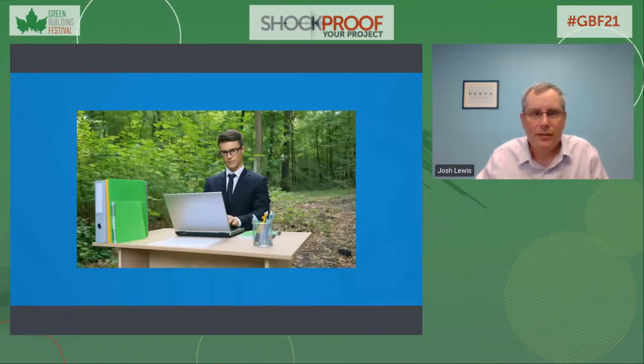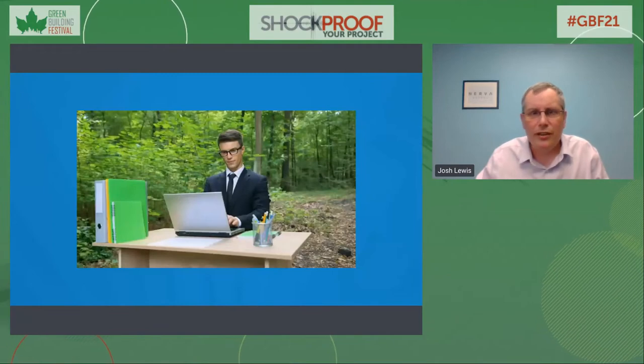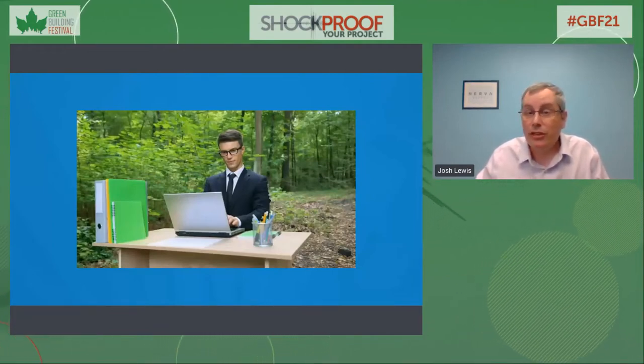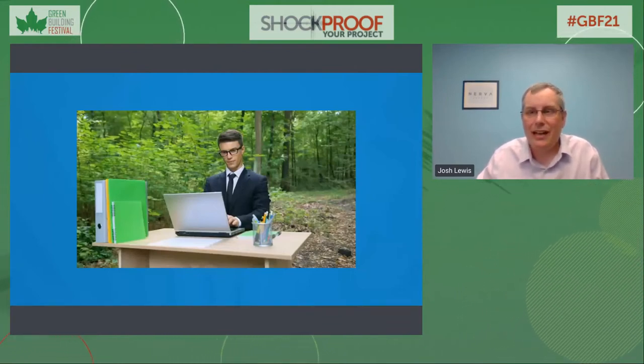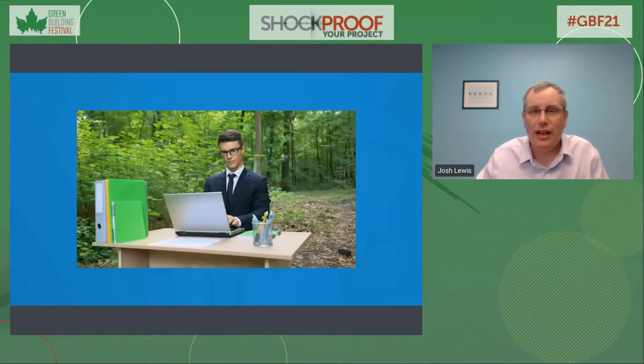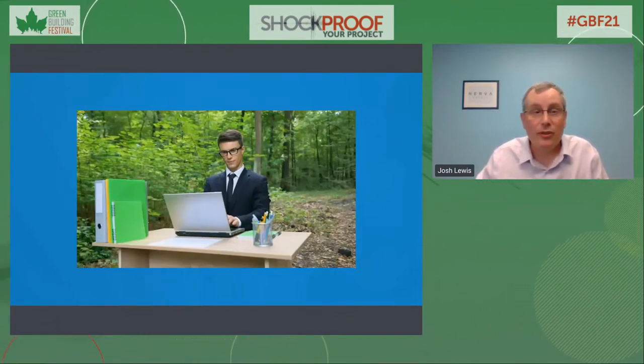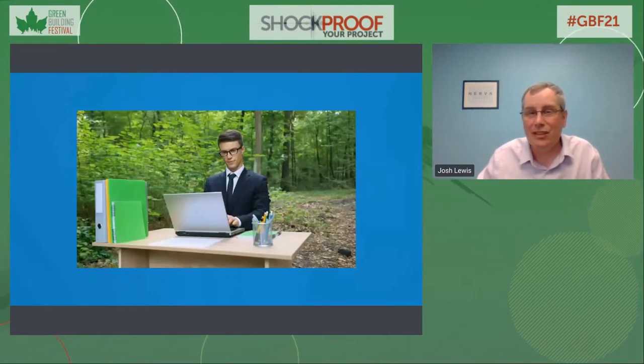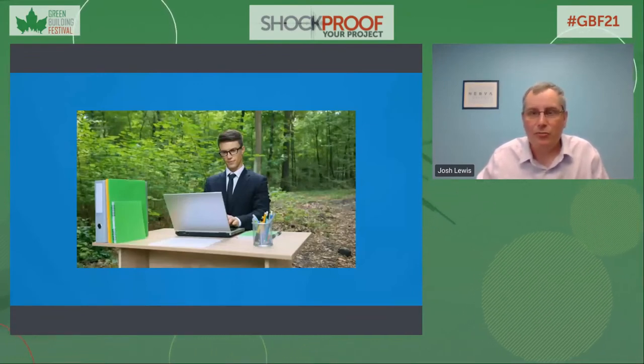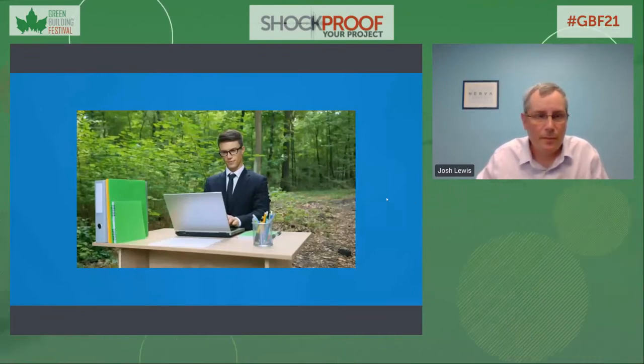The other related strategy for using fresh air strategically to create a healthy environment is called flushing, which involves setting up the HVAC system to bring in copious amounts of fresh air at a defined time, such as for two continuous hours after the building becomes unoccupied every day. This can be very effective at removing contaminants without necessarily having a very large impact on energy efficiency.